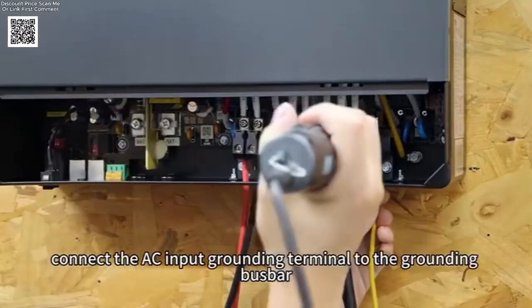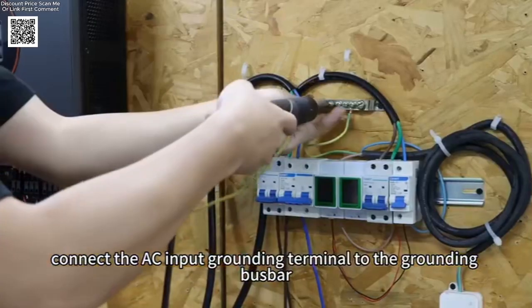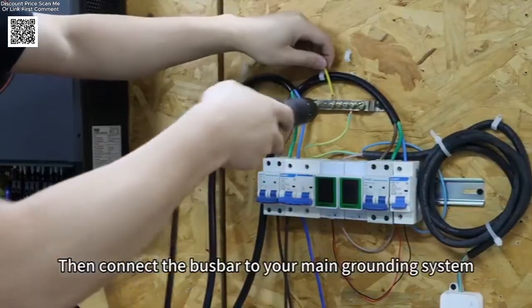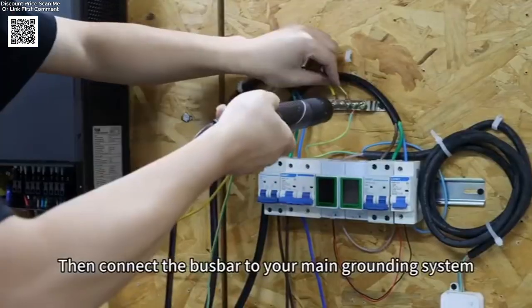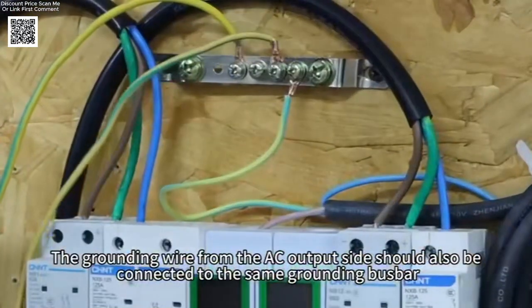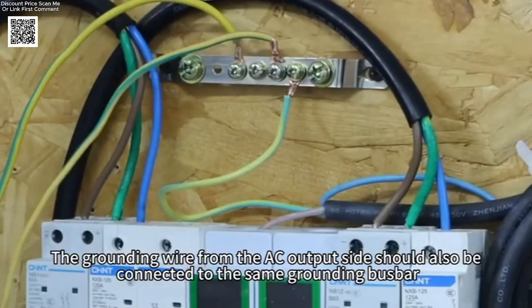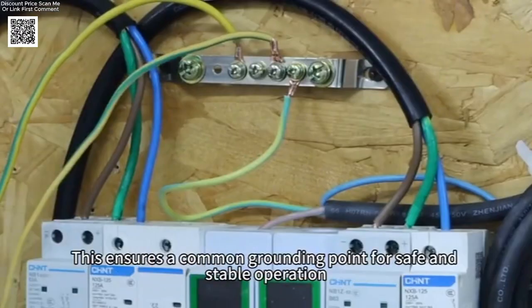Next, connect the AC input grounding terminal to the grounding busbar. Then connect the busbar to your main grounding system. The grounding wire from the AC output side should also be connected to the same grounding busbar. This ensures a common grounding point for safe and stable operation.